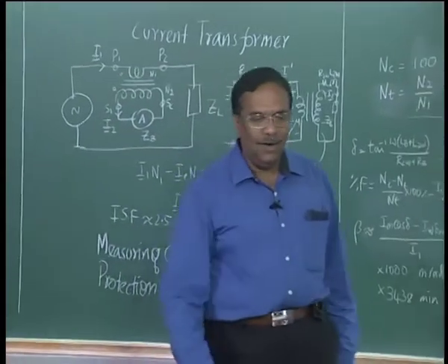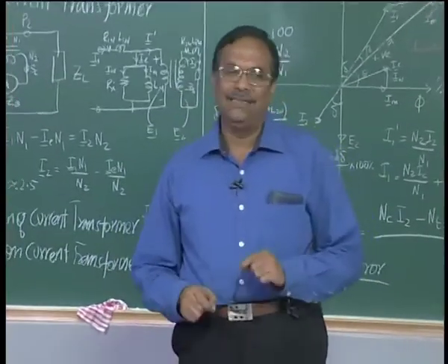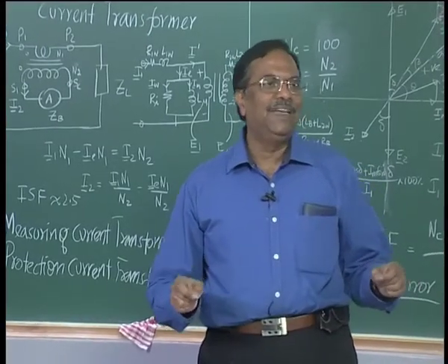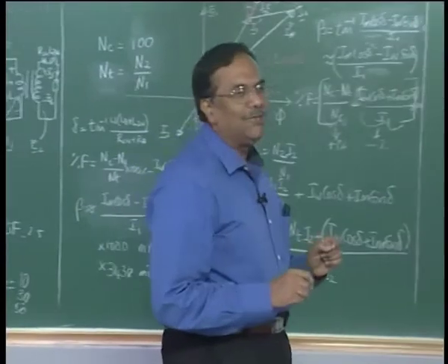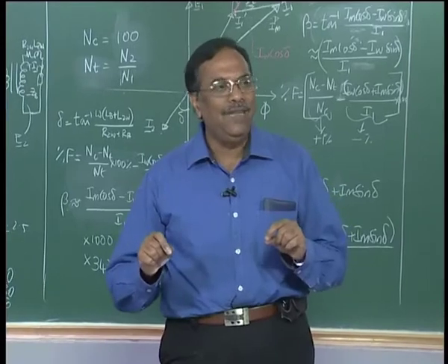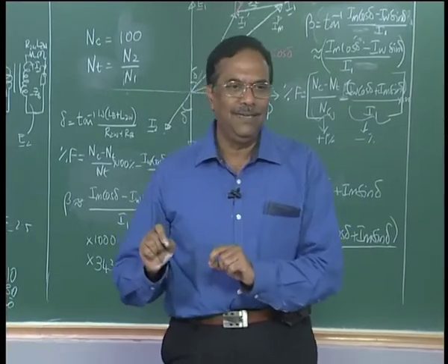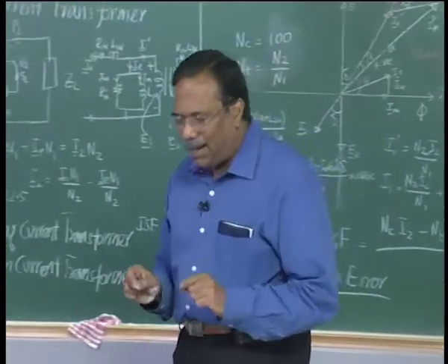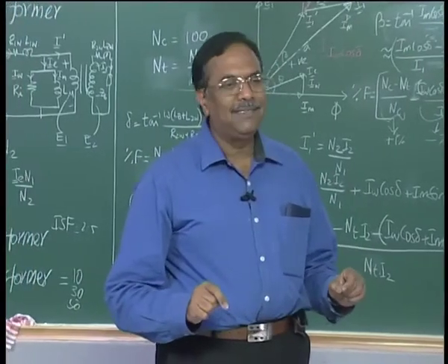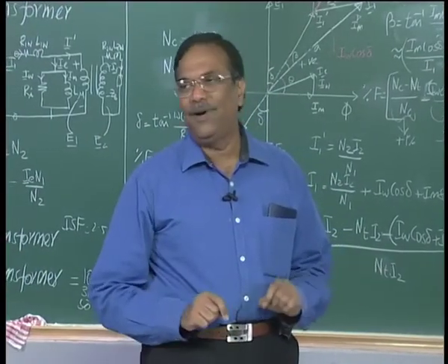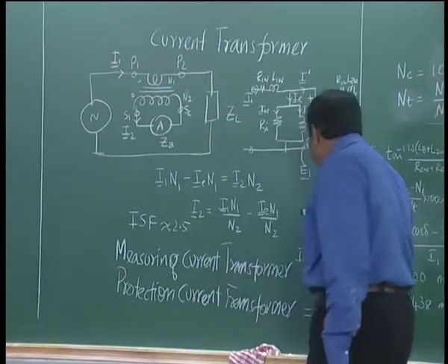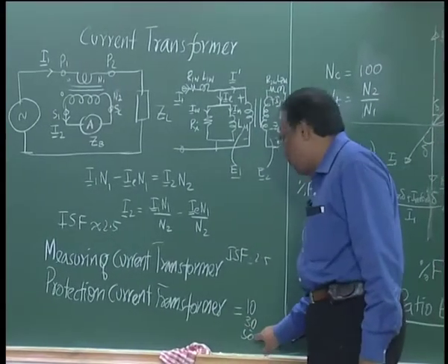This again will be enforced by the user. The user will try to calculate the probability of getting 50 times or 100 times the short circuit current. When we design a power system, we also design it to have a limit on the short circuit current. We intentionally introduce elements in series with the lines so as to limit the fault current. So based on that we may have a security factor of 10 times or 30 times or 50 times.